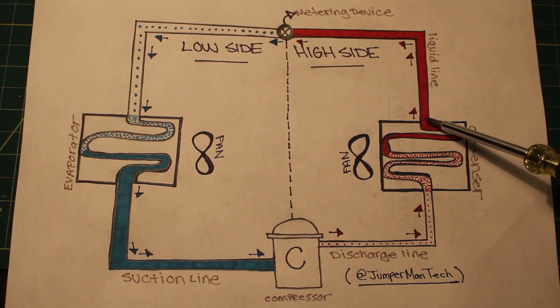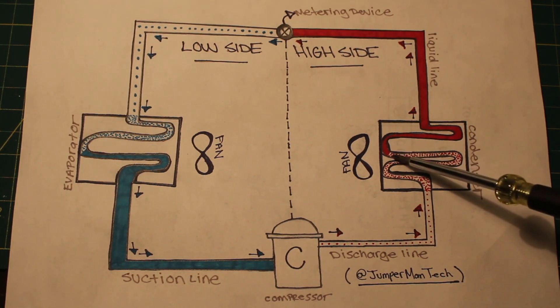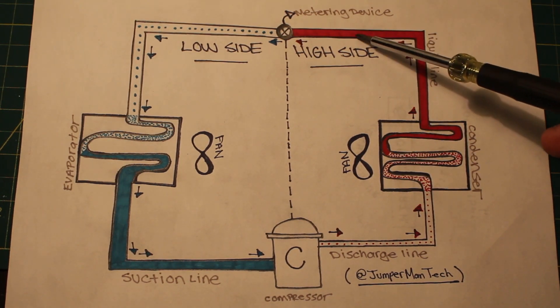So leaving our condenser, we are a high-pressure, high-temperature, sub-cooled liquid. Sub-cooling is a temperature difference between the refrigerant saturation temperature, which is right here halfway through our coil, and our liquid line temperature.